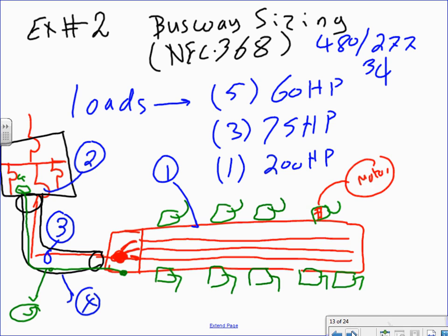That's basically it for the generator. Your generator math will be identical to this generator. So you have to go find the overcurrent protection device, the conductors, and all these systems. Any comments, guys? Any questions? Do you need a 5-minute break before we jump into the busways, or shall we jump into the busways? Five? Okay. I have 2 examples about busways, and then that will be it.